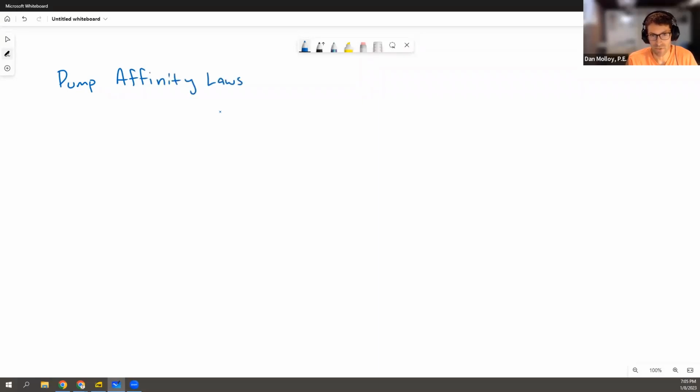And I'll jump right to the pressure, although it's usually presented, and it is in the reference handbook, as head. But suffice it to say that that's the same idea as pressure, is related to the ratio of the speed, the RPM, squared.